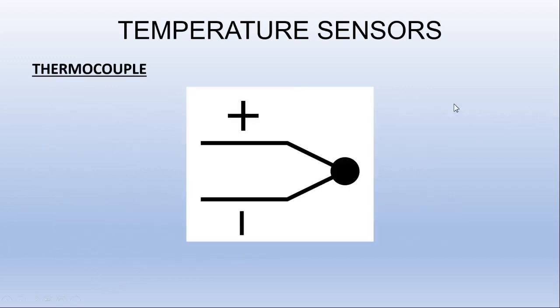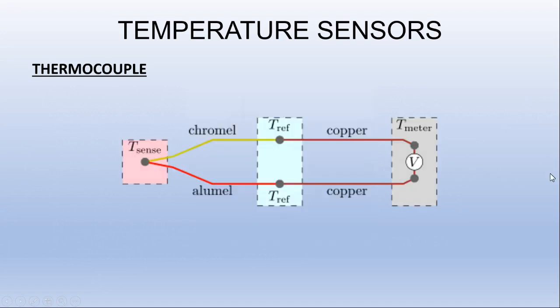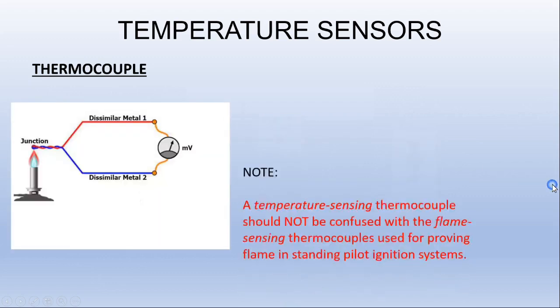Here's an electrical symbol of one. In this case, it shows the positive and negative polarities, and this represents the sensing junction. Here's one that's actually used in a thermometer, but that voltmeter probably has gradients on it to represent temperature. And in this case, there's a sensing end with chromel and alumel wires. Here's the reference point, or the reference junction. And then from there on, you just need basic copper wiring to transmit that circuit to the voltmeter.